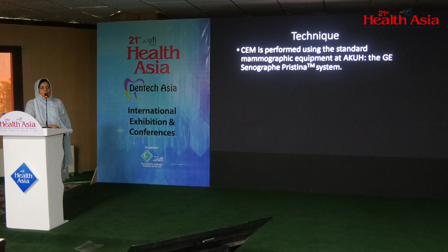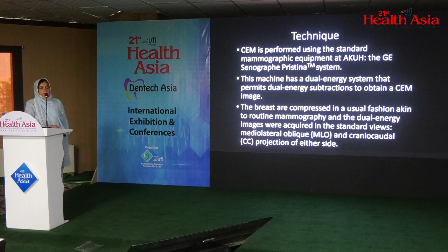So how is it performed? CEM is performed using standard mammographic equipment at AKUH, the GE Senographe Pristina system. This machine has a dual energy system that permits dual energy subtraction to obtain a contrast enhanced image. The breasts are compressed in the usual fashion akin to routine mammography, and the dual energy images are acquired in the standard views, MLO and craniocaudal, of either breast.